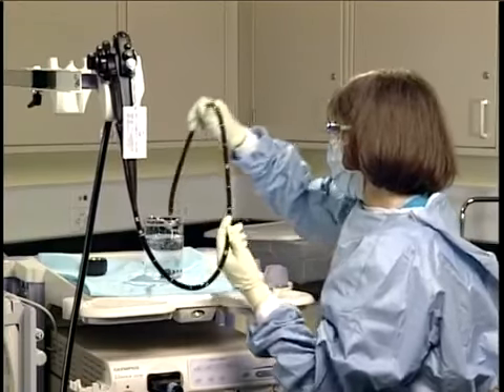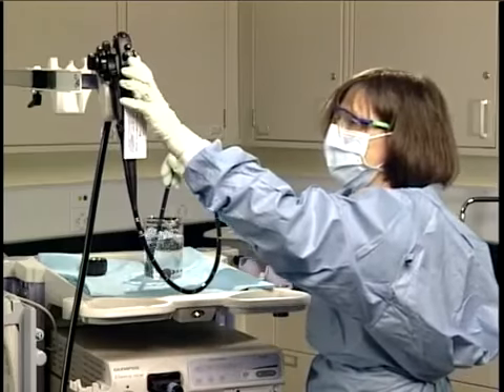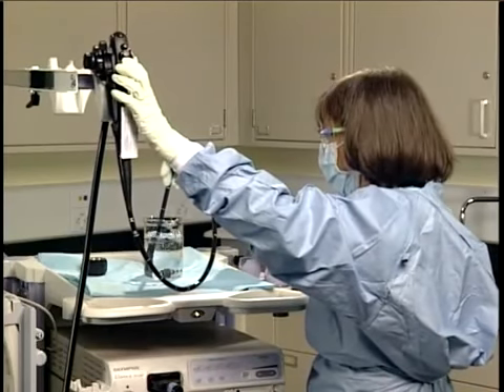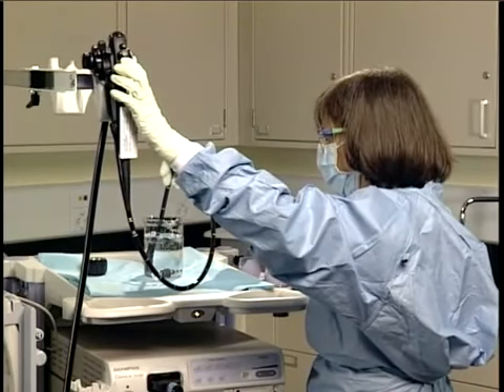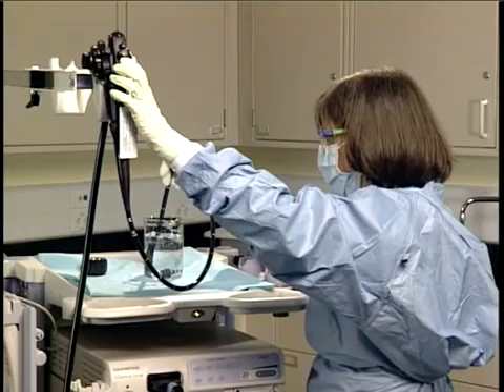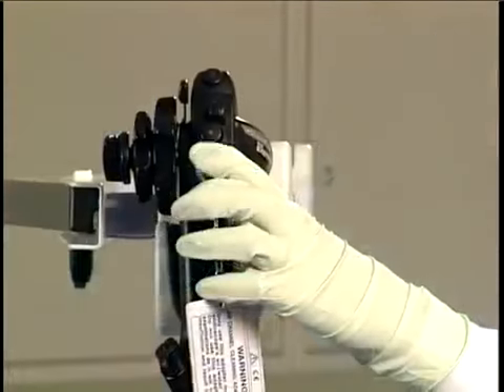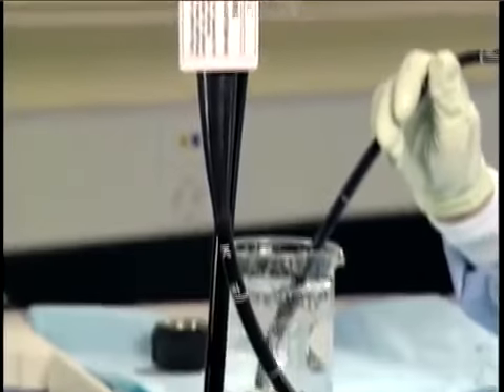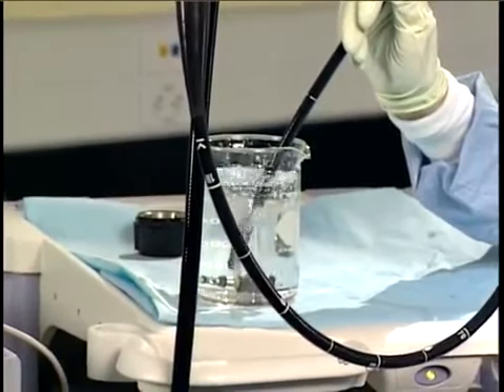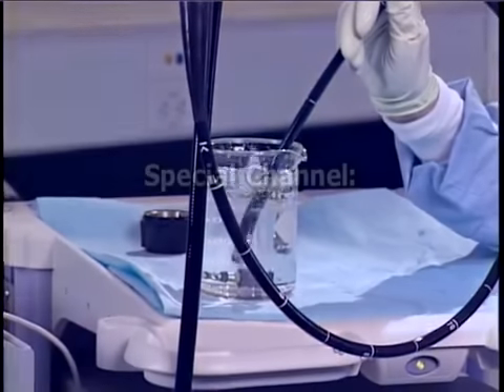Immerse the distal end of the endoscope in the detergent container. Depress the air-water channel cleaning adapter valve for 30 seconds. Release the valve to feed air through the air-water channel for 10 seconds.